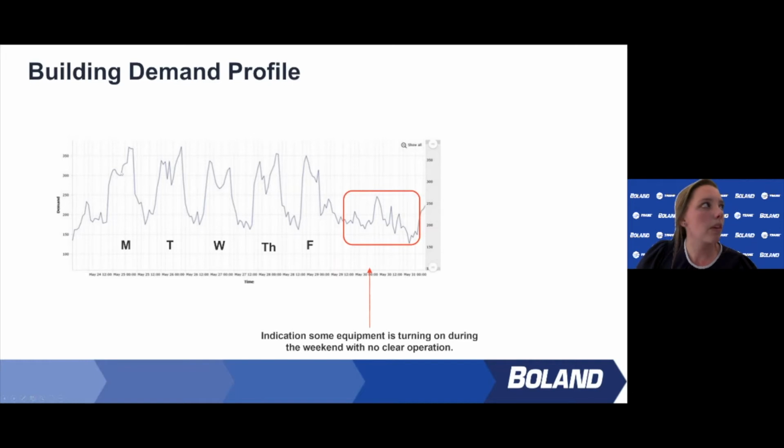We see a slight drop in the afternoon. That could be people going out to lunch, whatever. And then it increases again in the afternoon. And this is normal. Again, it's like the solar load, depending on just how the system has to keep the building conditioned. And then once the building's unoccupied, systems are turning off, the equipment, we see it decrease at nighttime. So that's good. It's found its base load while the building's unoccupied.